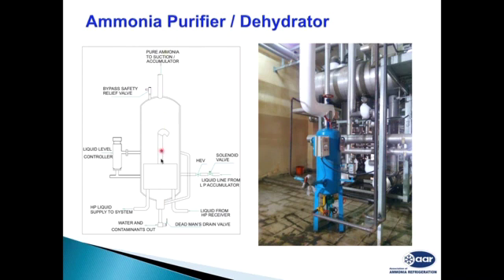If there is water or oil, it will accumulate at the bottom. Normally, when it is filled with the ammonia, frosting will be there on this unit, on this complete pipe. When there is no ammonia, the frosting will go, and when it is water or oil, the frosting will go at the bottom pipe, and you can remove it using the dead man's valve.